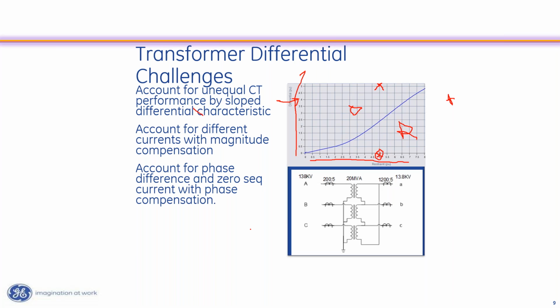And so if you look at where my CTs are sitting out here, on the outside of the actual windings, right? So right there's my CTs. And so that means that if I have 100 amps flowing out that 13.8 kV winding, I only have 10 amps flowing in to the 138 kV winding. So I have to accommodate that coming into the relay. I can't do that math in my head, I'm not going to attempt to. But coming into the relay, I've got a different quantity as well. So I've got to account for that in some way. And the way that I do that in a transformer is I do magnitude compensation. We'll talk about that a little bit later.